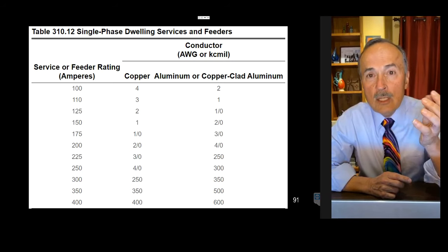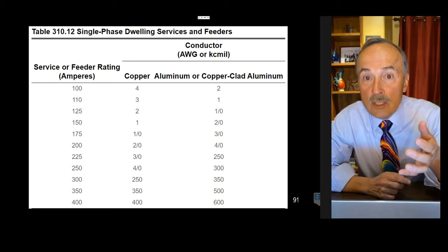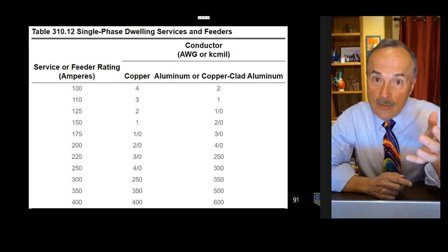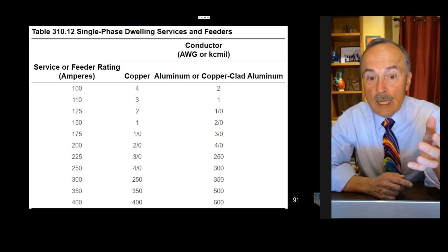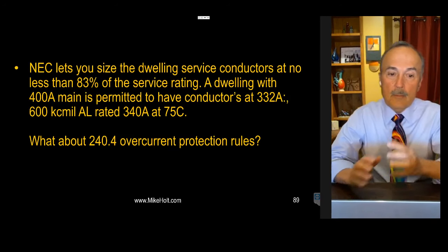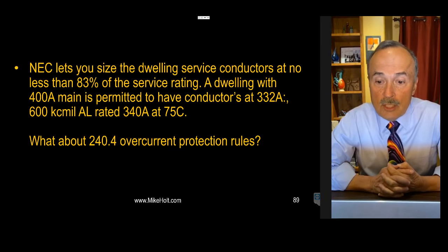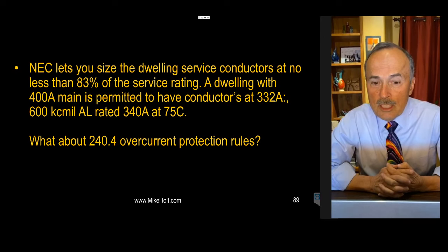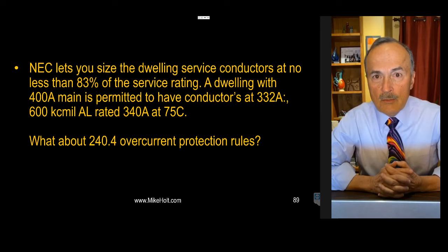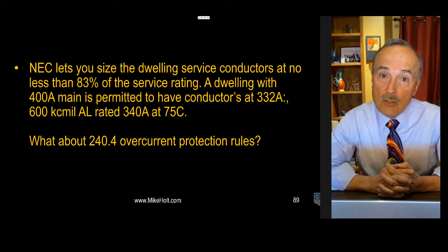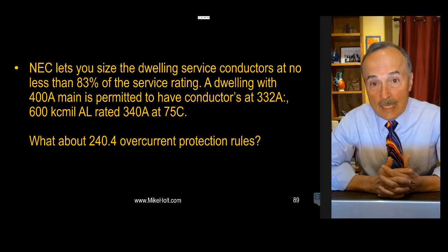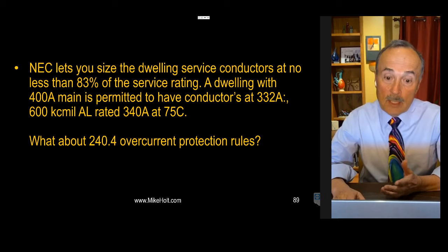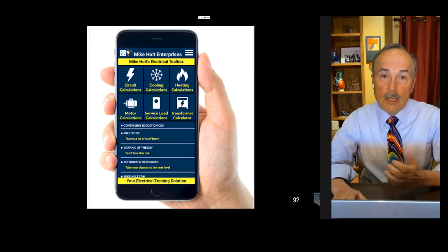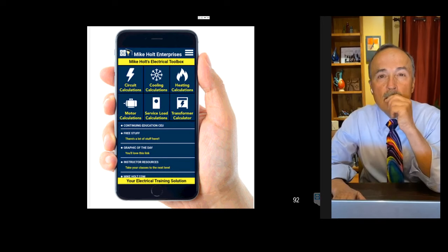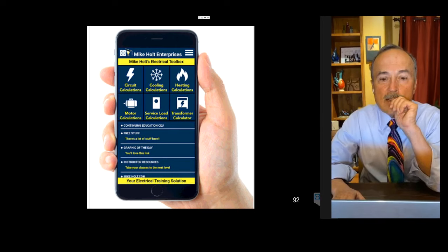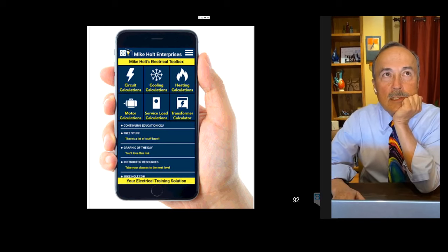I submitted a public input to have this table removed and simply take the 83% as part of the calculation in Article 220. Do your load calculation, and if you calculate 200 amperes, take 83% of that, and that's how you size the service. Then you size the protection at 83%, and then you size the conductor to the rating of the protection. So, back to the question here. Mike, the NEC allows you to use an 83% adjustment. But if you use it, then the overcurrent protection rules are in conflict. And the answer is yes, that is true. It's been that way for 100-something years, and probably nobody even thought about that. But I did, and they rejected my public input. So that's what it is.